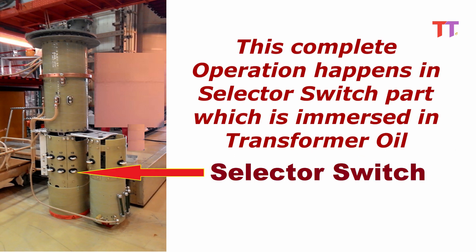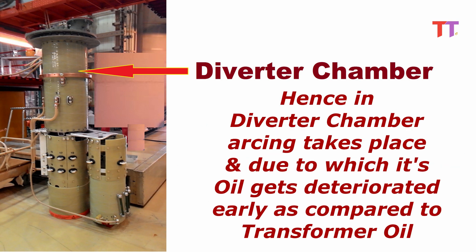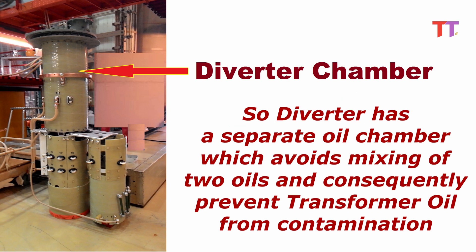This complete operation happens in the selector switch part, which is immersed in transformer oil. The other part of OLTC, called the diverter chamber, is at the top and has a separate oil chamber isolated from transformer oil. This diverter is used to divert minor arcs caused during OLTC operation. Arcing takes place in the diverter chamber, causing its oil to deteriorate earlier compared to transformer oil. So the diverter has a separate oil chamber which avoids mixing of the two oils and consequently prevents transformer oil from contamination.